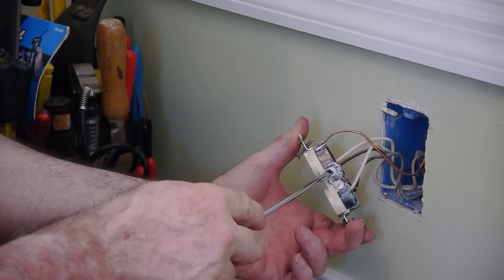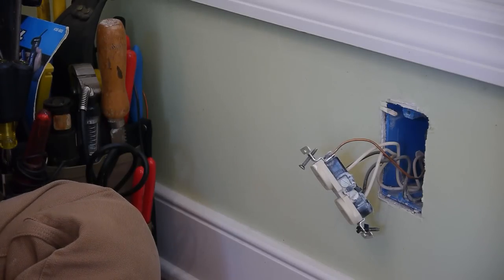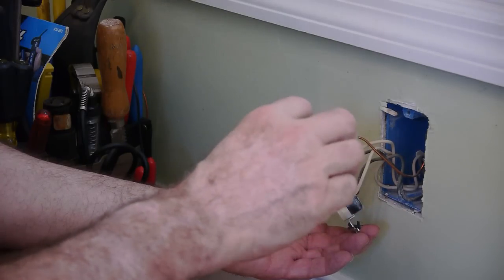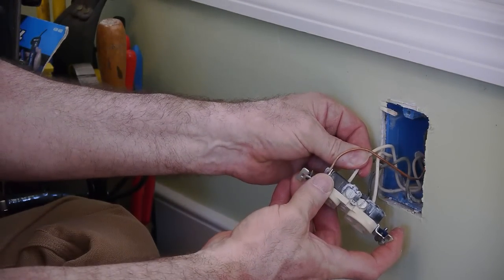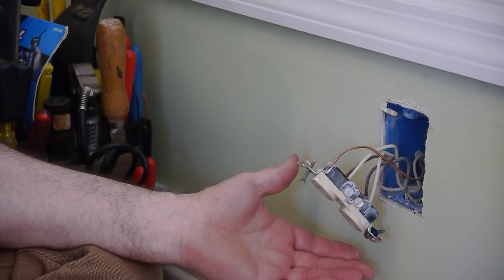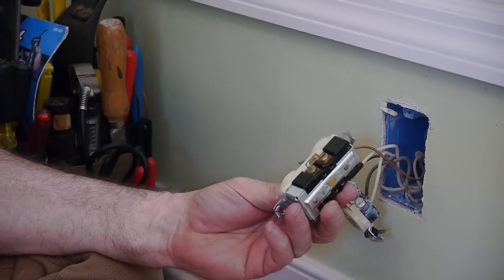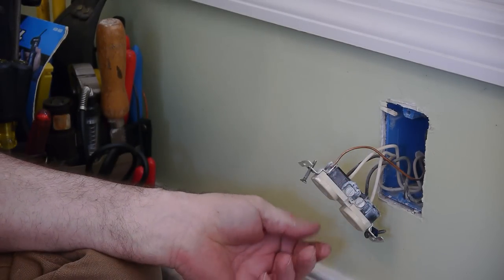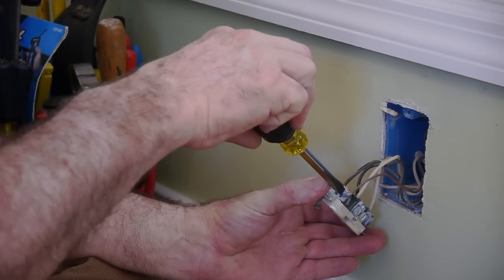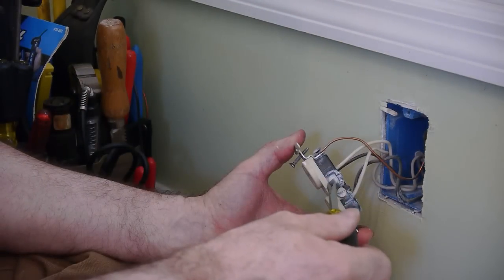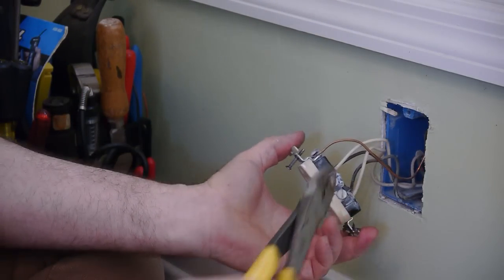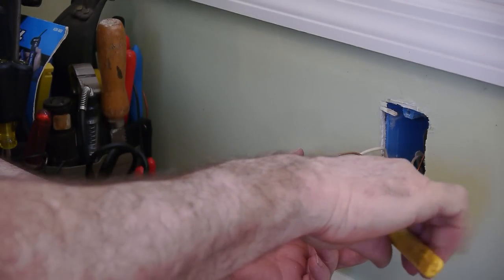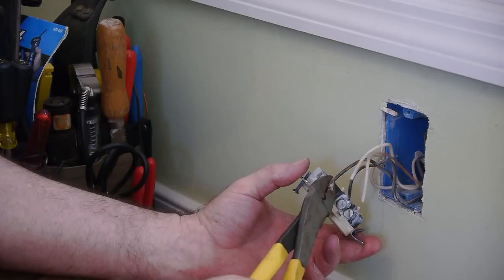And now this is really hard to tell here. Now that's loose. Right screwdriver. So that should be tight there. It's not. This one's tight. Let me see if that pull out. Now that's held in by a spring. So there's no clamping going on there. So I'm going to take it completely apart and put it in this outlet that I salvaged from another job. It's a high quality outlet. So I'll fast forward through this. You don't need to see all this stuff. That's not coming out. So I'll have to snip it.